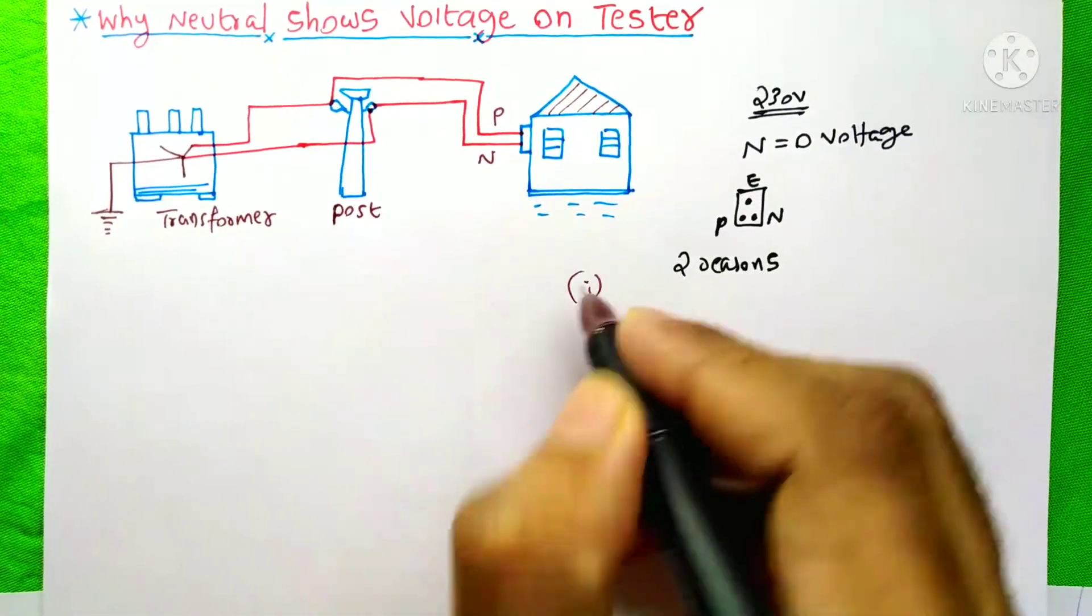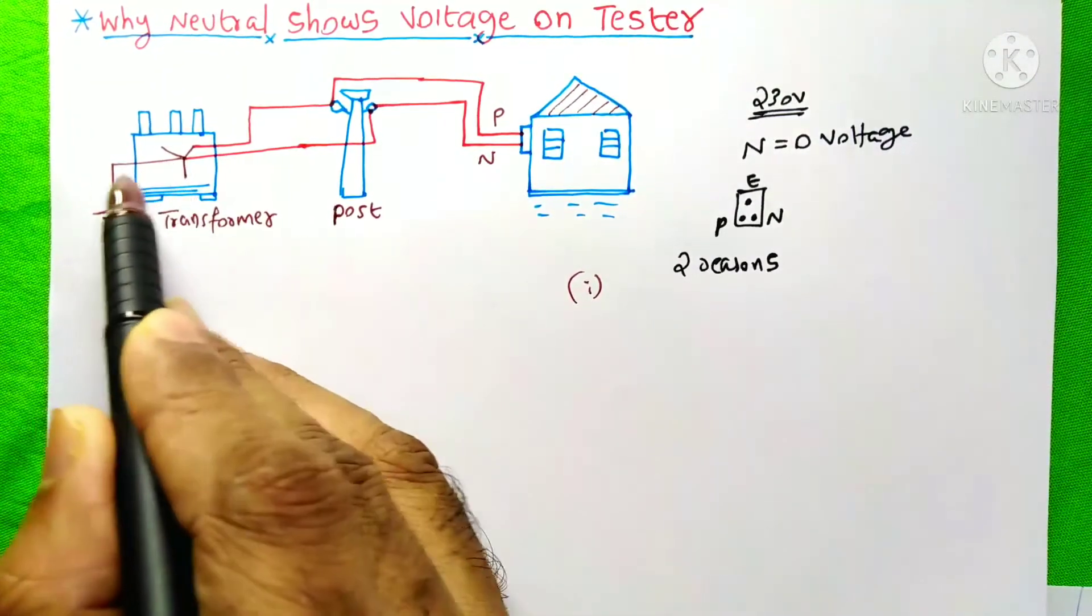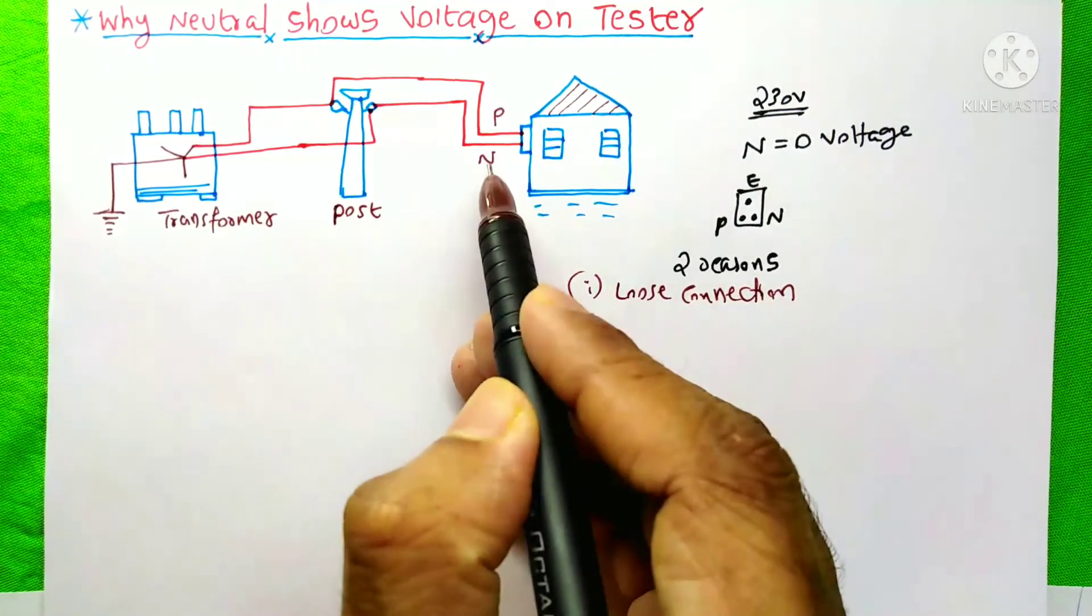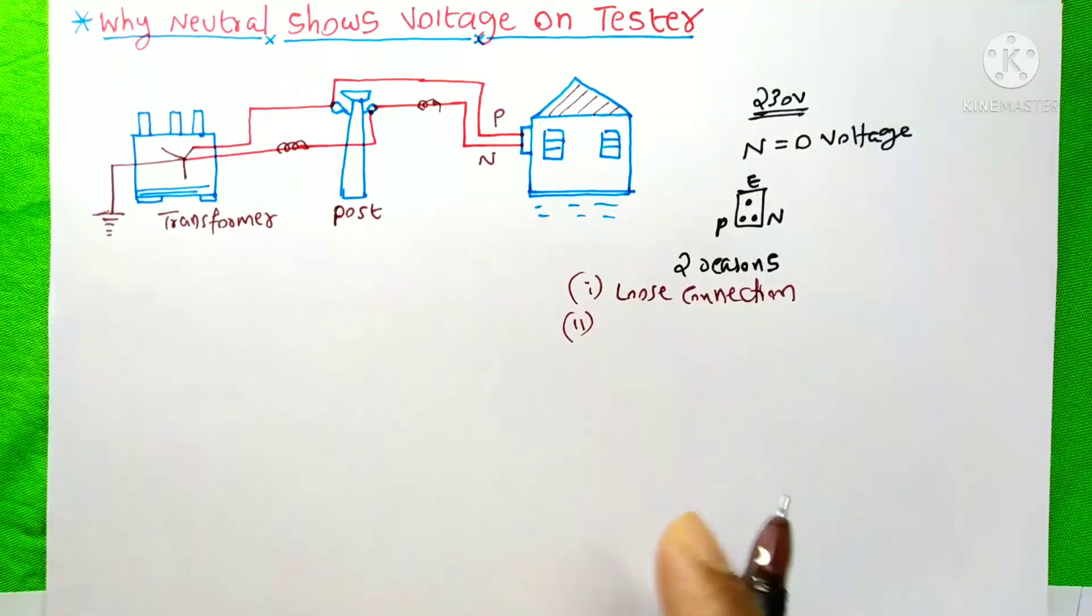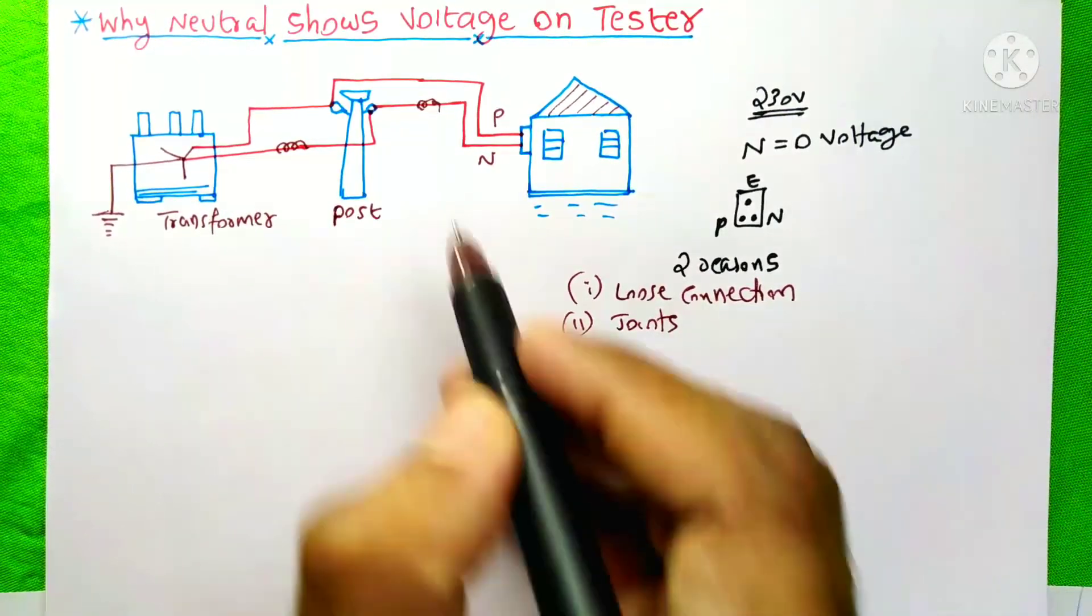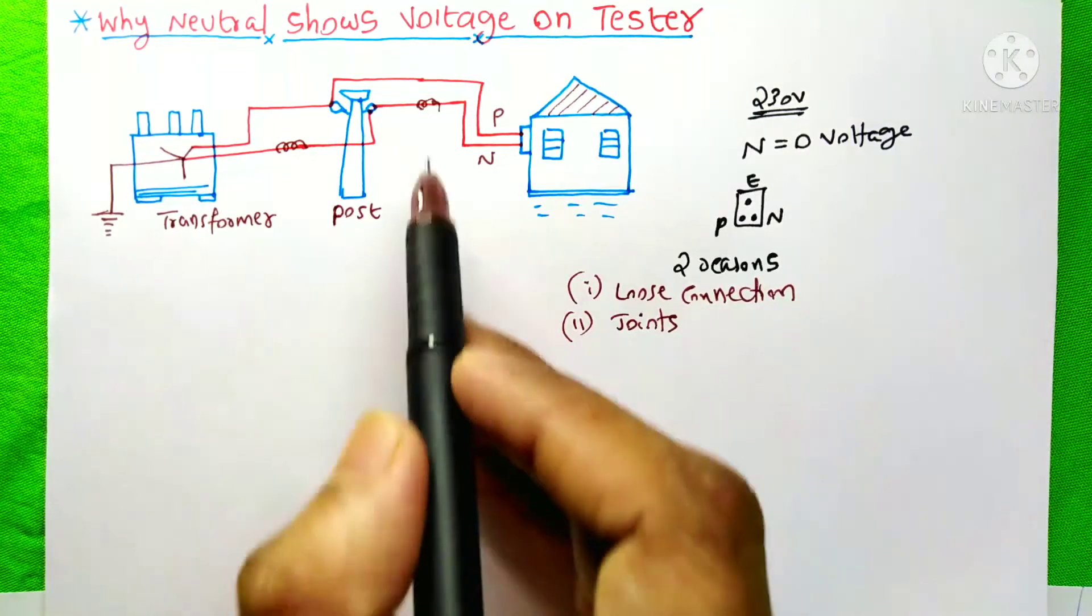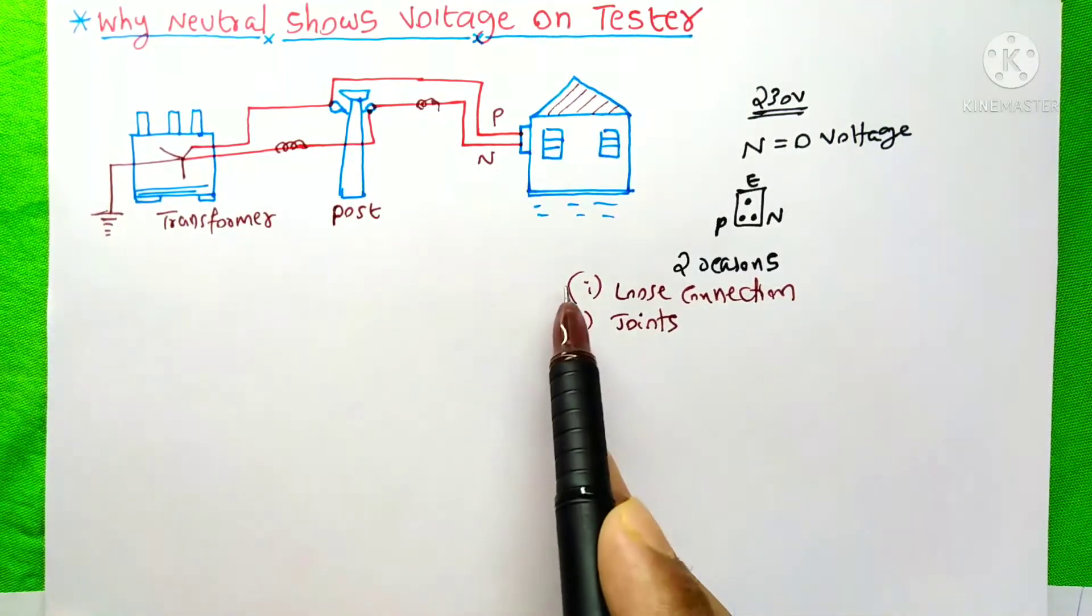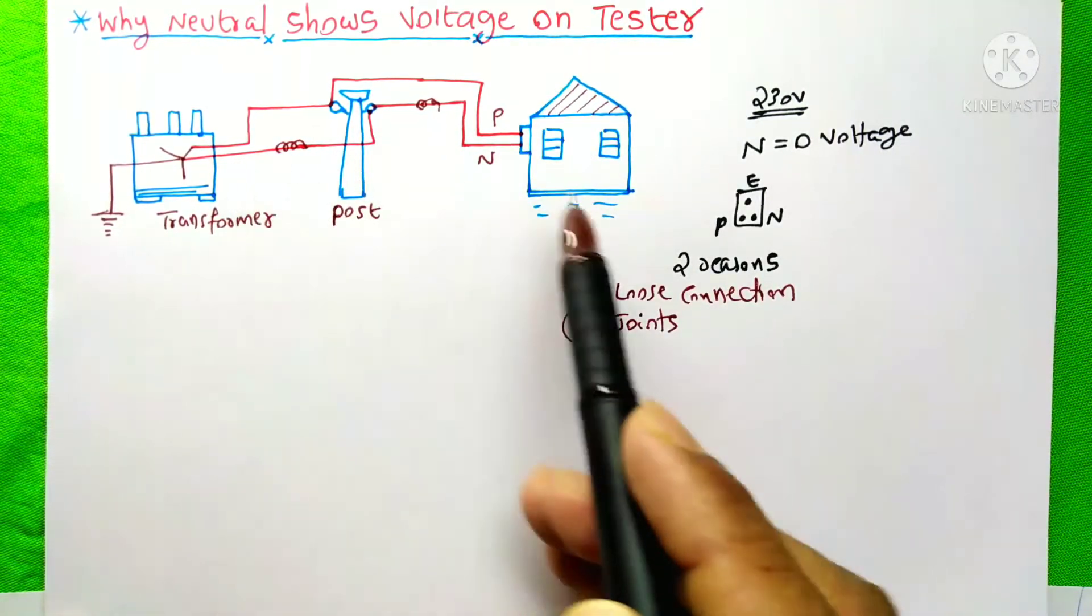The first case is some loose connection is occurring at the transformer neutral connection. Due to this loose connection, the return current through this neutral is not earthed properly. The second case is joints has been made somewhere on this neutral wire. Due to the improper joints on this neutral wire, the neutral current is blocked from this earthing. Either of these two reasons will cause the voltage on this neutral wire.